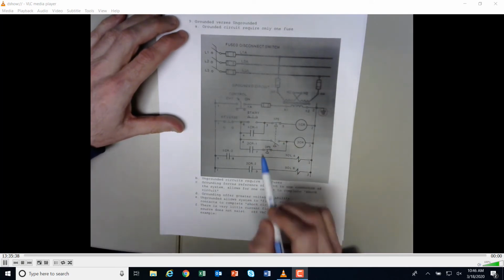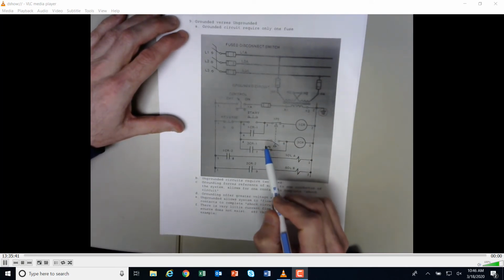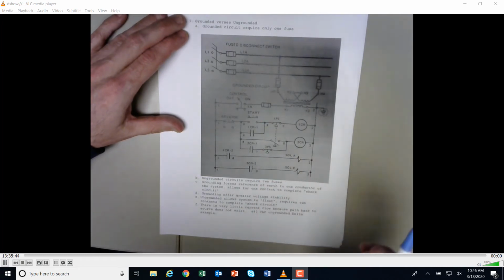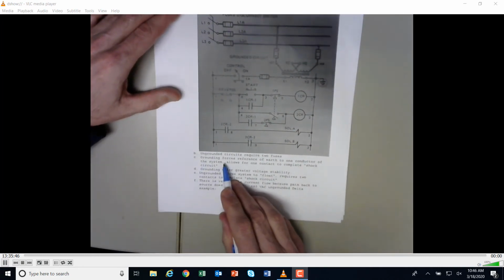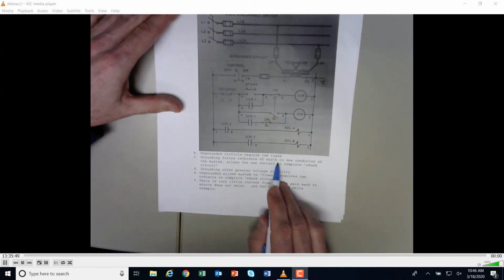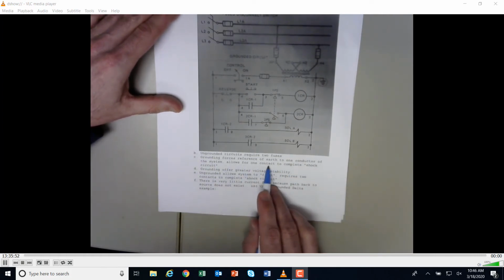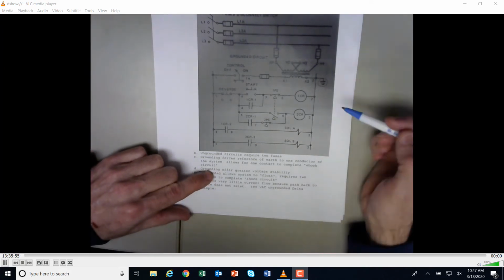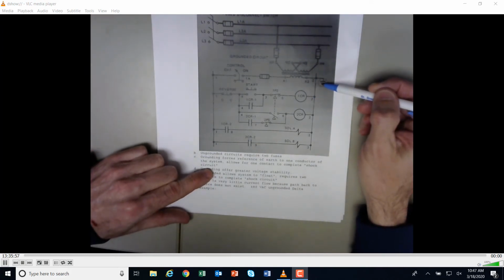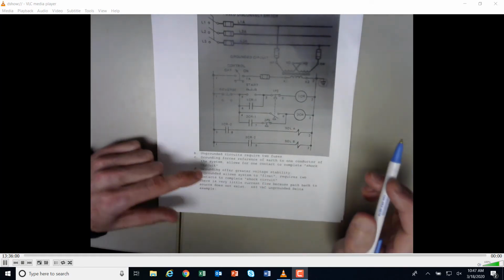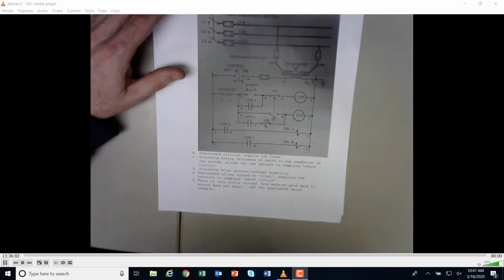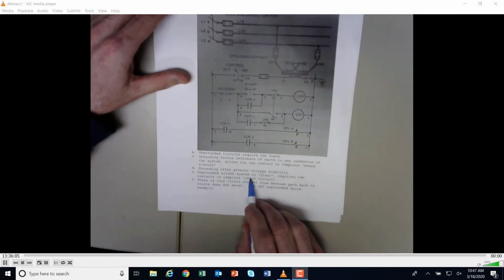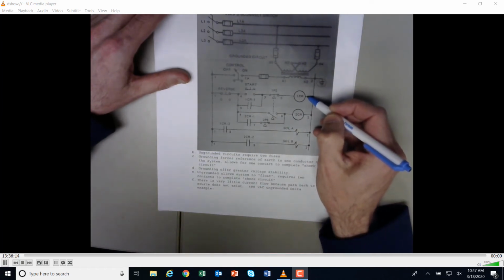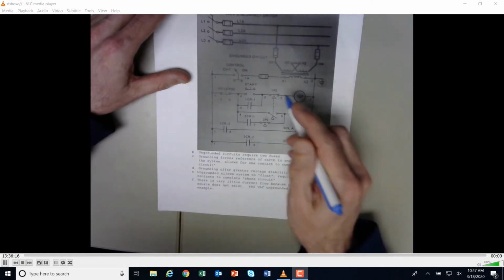You have to find where the ground fault is, or you're going to keep blowing fuses. So grounding forces reference to earth to one conductor of the system and allows for one contact to complete the shock circuit. So we get the one contact, it's grounded to earth, and we have the shock circuit. Ungrounded systems allow the system to float, and it requires two contacts to complete the short circuit. So now we just don't need one short right here to ground that's going to blow the fuse.